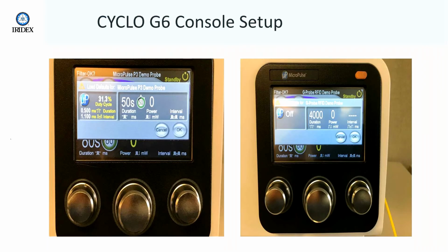Here's a picture of both the micropulse mode and continuous wave mode. Micropulse mode on the left, continuous wave mode on the right. You can see that on the right, the UP or micropulse is off. There is a duration of 4,000 milliseconds. You'll adjust the power to the desired power and then push OK. On the left side, you have micropulse mode, which tells you the duty cycle, 31.3% or 0.5 milliseconds on, 1.1 milliseconds off. And then you have a duration of 50 seconds, and you can set the power with the middle knob there and push OK.